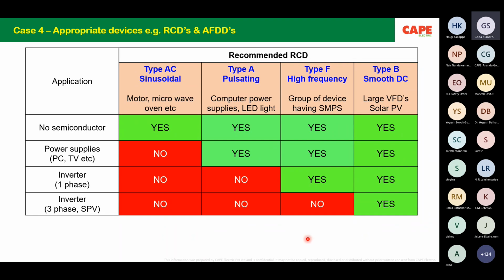Explanations are provided. Now the difference is, for example, if you have LED lights in your house or in your office, then you are supposed to use a type A RCD, not a type AC. If you have a solar PV installation on your rooftop and the inverter doesn't have simple separation, that means there is no isolation transformer, in that case you are supposed to use a type B RCD at the AC side, at the incoming power supply of your house, for example. So these are very much included in the standard.